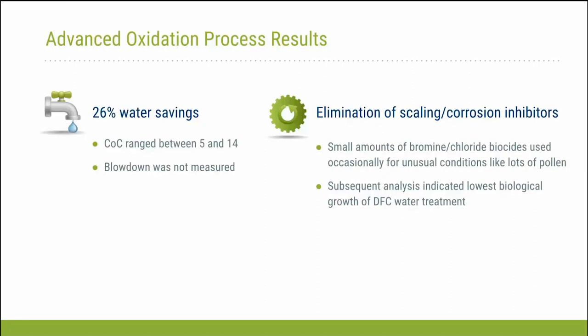They were also able to completely eliminate all the scaling and corrosion inhibitors they were using. They were still using a little bit of biocide on this one, but we conducted follow-up water sampling from the basins of the cooling towers, and this one actually had the lowest levels of biological growth of any of the systems tested at the Denver Federal Center. So it looks like they could have fully eliminated all of the chemicals being used on this one.